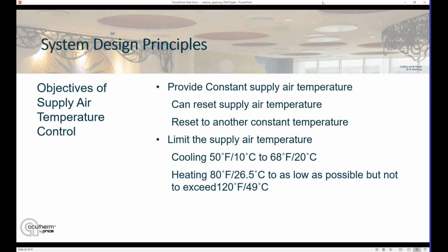But we try to say keep it as low as possible, because you really shouldn't need too hot an air to heat a modern building with good insulation these days. But they will operate as high as 120 degrees. Although the lower you can keep it, the better you are with stratification and being able to drive that warm air down. And lastly, we need a means to provide changeover between the cooling and heating modes.